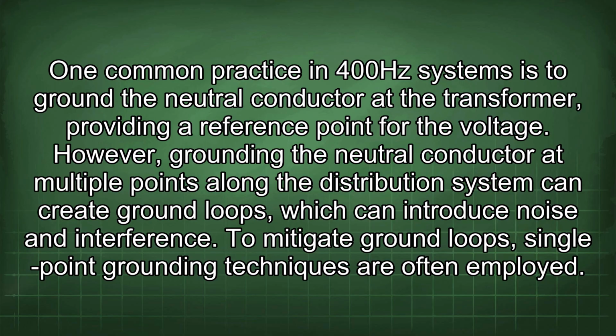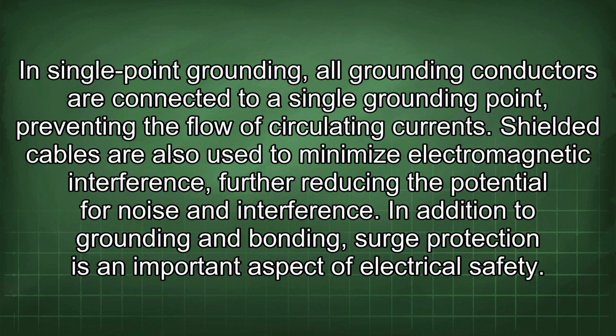One common practice in 400Hz systems is to ground the neutral conductor at the transformer, providing a reference point for the voltage. However, grounding the neutral conductor at multiple points along the distribution system can create ground loops, which can introduce noise and interference. To mitigate ground loops, single-point grounding techniques are often employed. In single-point grounding, all grounding conductors are connected to a single grounding point, preventing the flow of circulating currents. Shielded cables are also used to minimize electromagnetic interference, further reducing the potential for noise and interference.